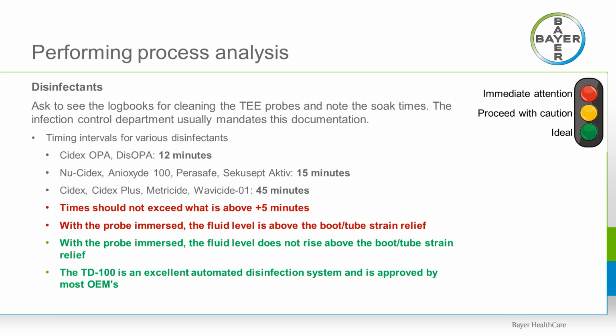So the questions are, is the probe being disinfected using an approved chemical? Is the immersion time being monitored, and is it being logged? How do the logged immersion times compare to what is actually recommended by the disinfectant manufacturer? Hospital policy or infection control usually requires logging of disinfection cycles.